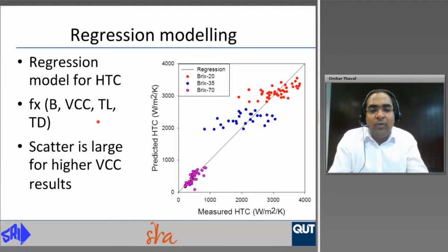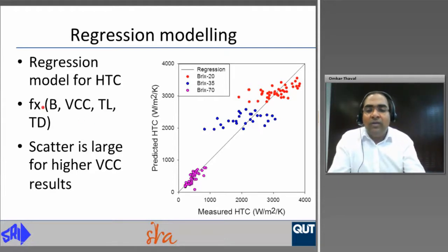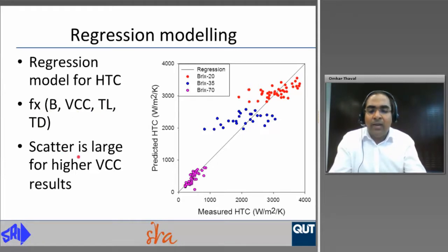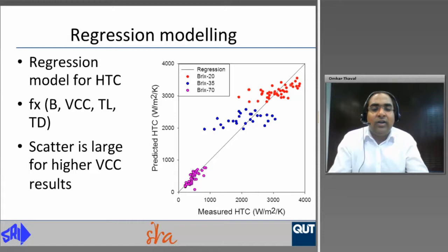The second objective of phase two is to develop a regression model for heat transfer coefficient. This is the first attempt to put together a regression model for heat transfer coefficient with all tube dimensions studied in this work. The equation is a function of brix, vapour condenser coefficient, tube length, and tube diameter. The scatter is large for higher VCC results, and work is still ongoing to improve this regression model.